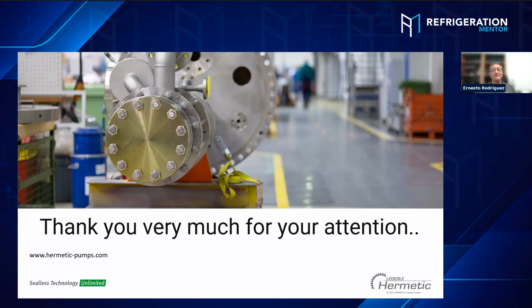Well, basically, with hermetic pumps, as I say, if the pump is running, don't touch it. If you see the pump is running smooth, there are no noises, don't touch it, don't open it. If someone says I have a one-year maintenance I need to do, I say, well, the pump is running? Yes. Any problems? No. Leave it. Don't open it, because sometimes when you open the pump, you can make a mistake when putting it back together. Basically you check that the system parameters are correct.